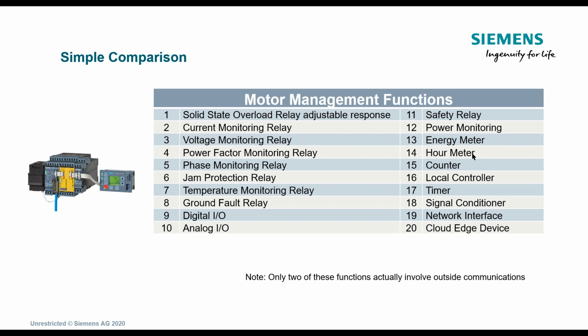I like the hour meter because there is a lot of maintenance, or preventive maintenance, on motors, and applications are usually a calendar event. So every 6 months, go out and grease these bearings, check the alignment, check the motor junction box, et cetera, et cetera. But one of the key things is that it is important to be able to give really good metering for that system. And again, sometimes you might go for 6 months and that motor's turned on twice, but you're out there already doing the PM on it.